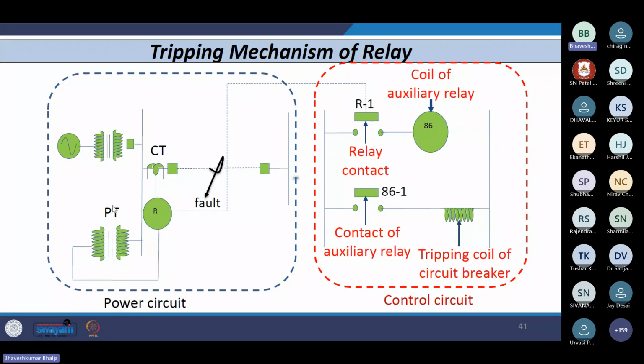Now, why this some time? So this time, as per IEC standards, because usually in our country we follow IEC standards. All the utility personnel follow IEC standards. So whenever the breaker becomes open, the utility person has to wait for some time delay. This time delay is decided based on the reclaim time of the circuit breaker. Now what is reclaim time?